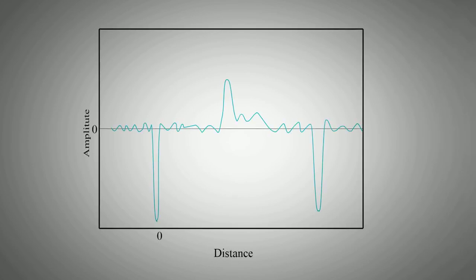Here is an echo curve that shows the amplitude of the reflections measured against distance. Examining the echo curve, we will be able to see some clear indications of the start of the probe, or reference, shown by the first negative amplitude dip.